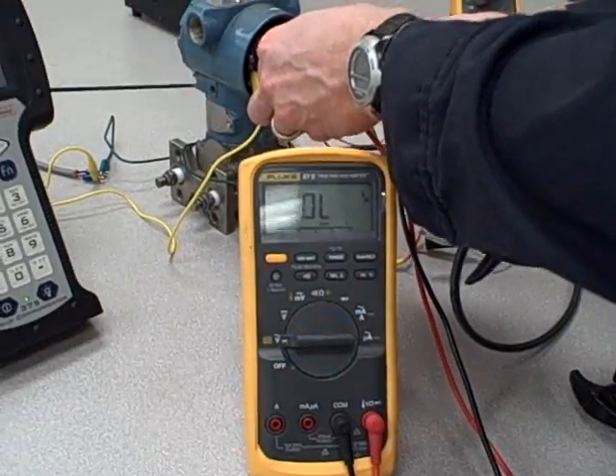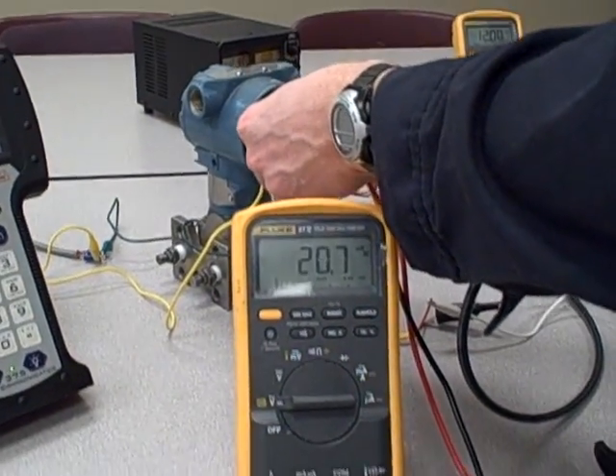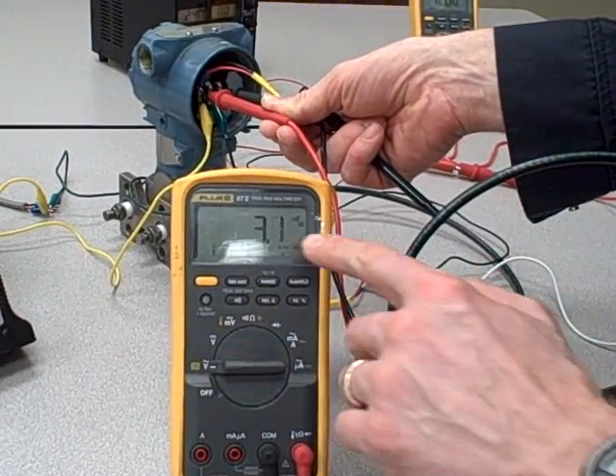If we take a look at the voltage signal here with our Fluke meter, while we retry communication, we'll see exactly why it can't talk. We're reading just a couple of millivolts noise voltage.